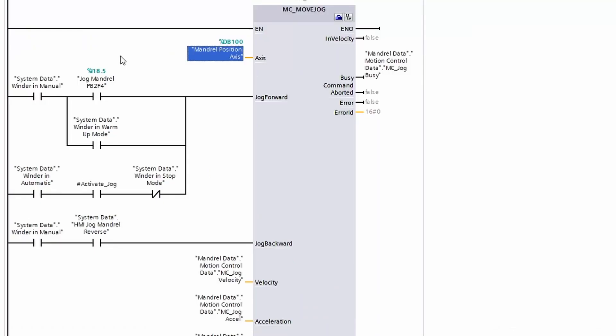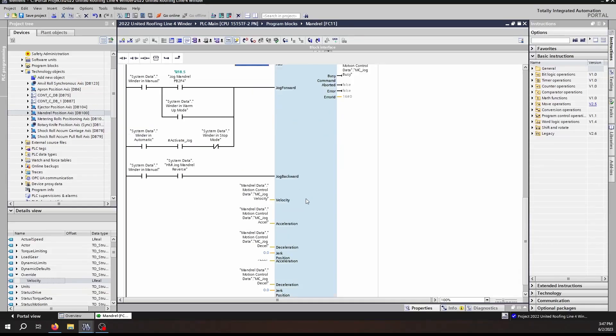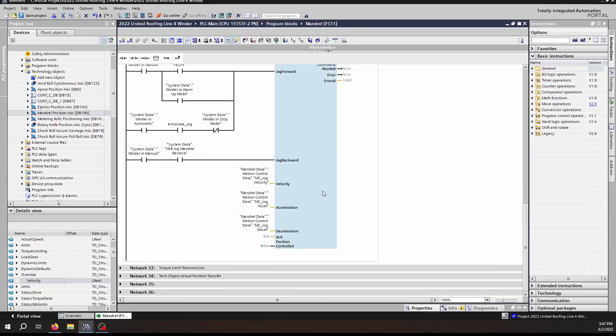As we continue down the inputs, we see a little bit different than we have seen on any of the other blocks. We have a Jog Forward and a Jog Backwards. These inputs are used similar to the execute bit in the MC Move Velocity, but with a slight difference. You have individual bits for forward and reverse. As with the other block, you have to maintain these inputs in order for the motor to keep running. I'll say that again: in order to keep the motor running, these inputs have to be maintained.